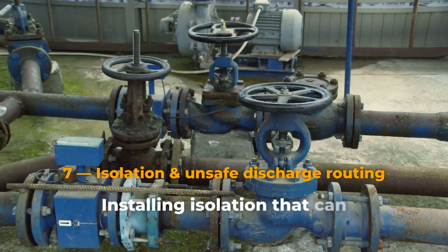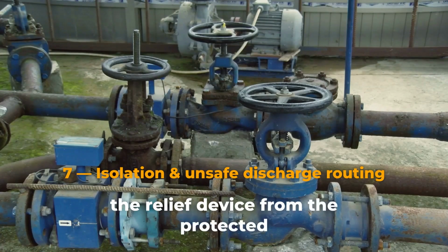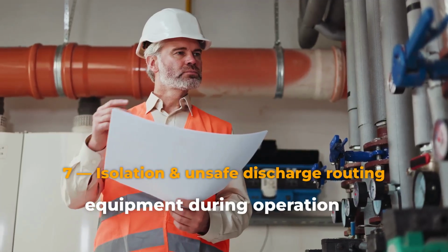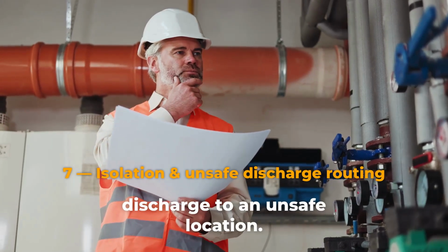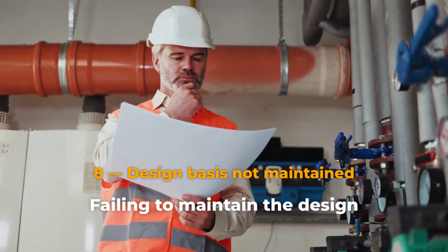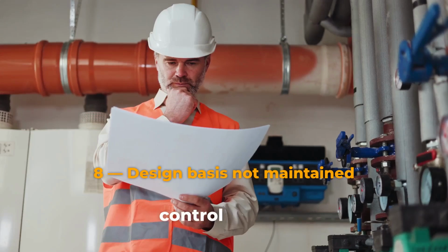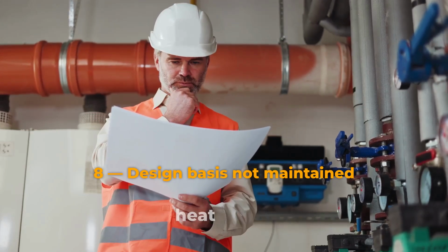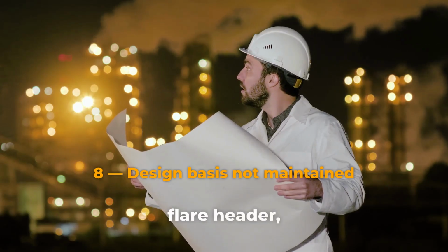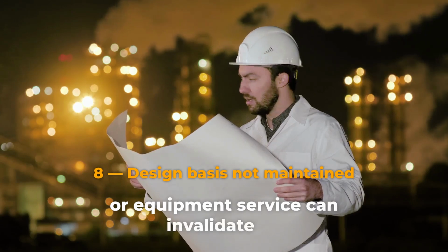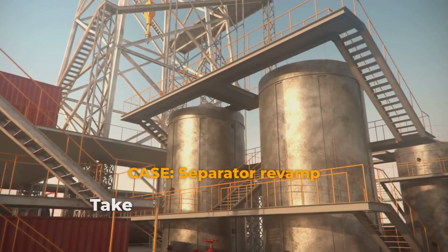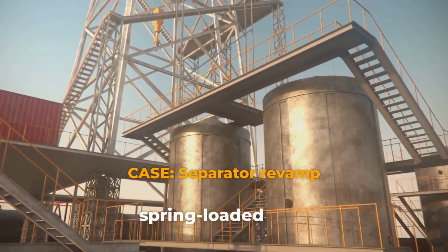Installing isolation that can separate the relief device from the protected equipment during operation, or routing discharge to an unsafe location. Failing to maintain the design basis. Changes in feed, control valves, operating pressure, heat input, piping, flare headers, or equipment service can invalidate an old relief study. Take a separator protected by a spring-loaded PSV.